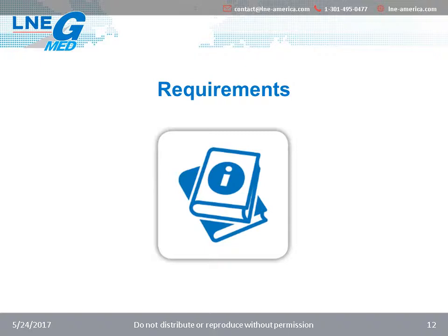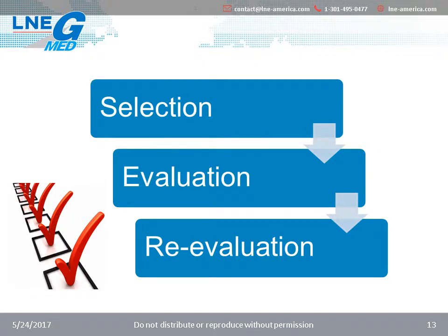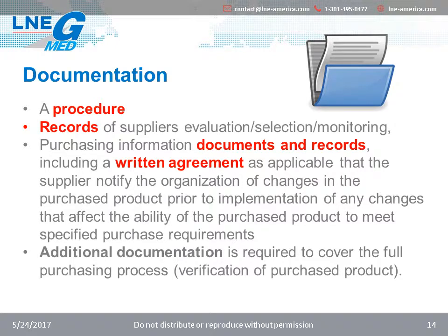Now let's talk more in detail about the supplier control requirements. As previously identified in the 2003 revision of the standard, the organization shall control the selection and evaluation of its suppliers, but also its re-evaluation. This remains applicable with the 2016 revision, in which requirements are now more specific. This means supplier control begins even before making the choice of using one, and continues until the organization stops using the supplier. Let's have a closer look at three main requirements: the documentation, the supplier control criteria, and the risk-based approach.